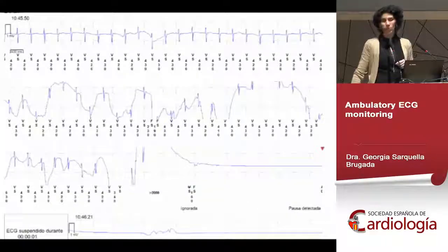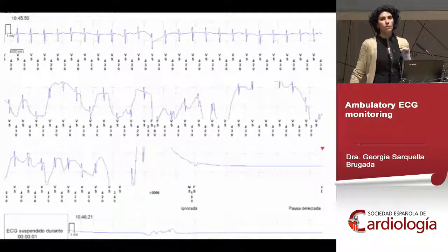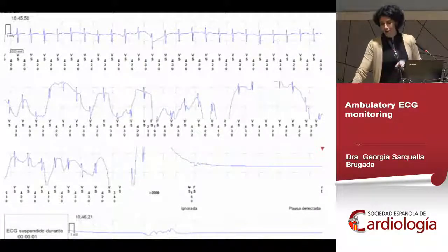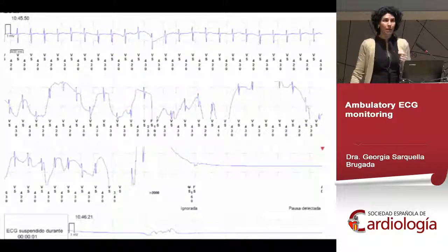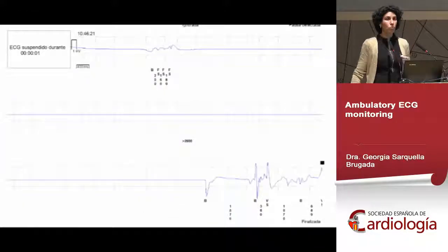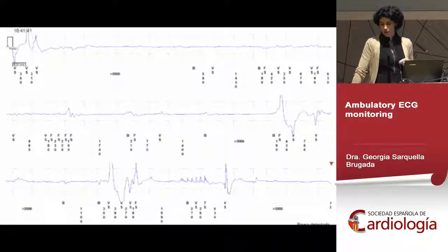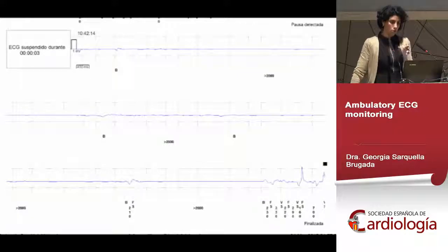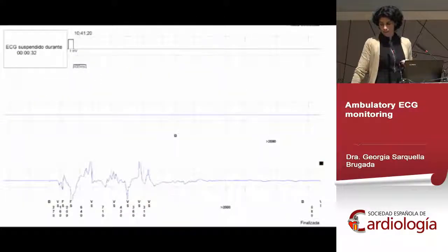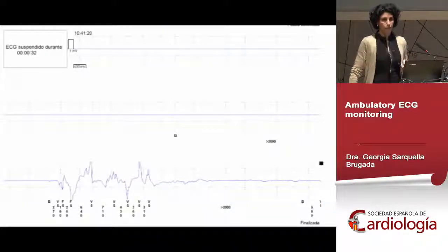And finally, there's a very important artifact: if you program the device before inserting it. That had happened to us once, not twice, just once. We learned that the first email we got from the system was an extreme bradycardia that we were really stressed about, till we found out that it was just before the implantation. Actually, that's the first try to put the device in, when we can see all the signals, and then we took it out because it was not deep enough, and then we put it back again, so we learned that we have to program after implanting to avoid that.